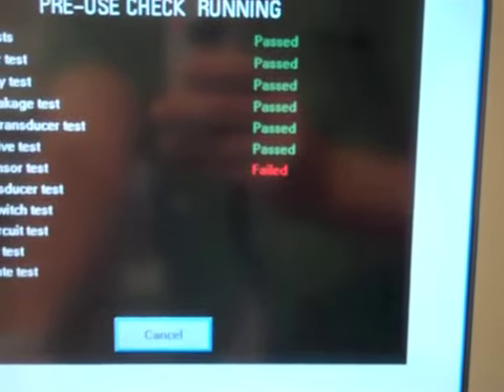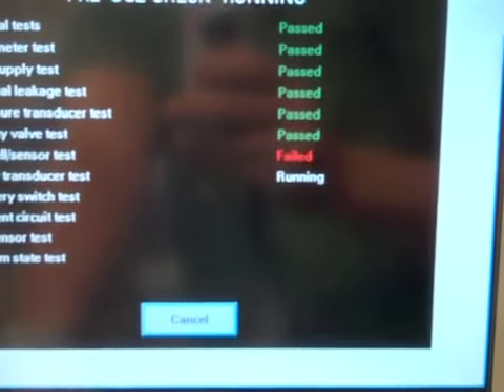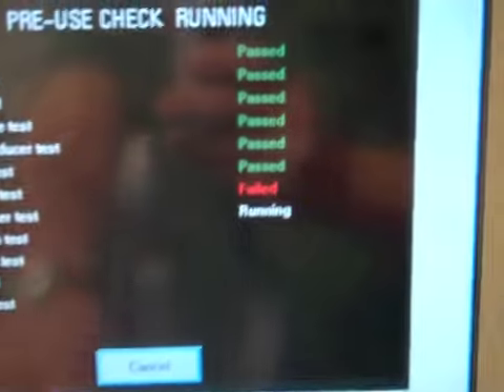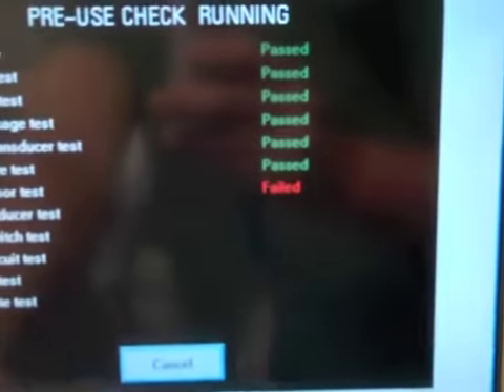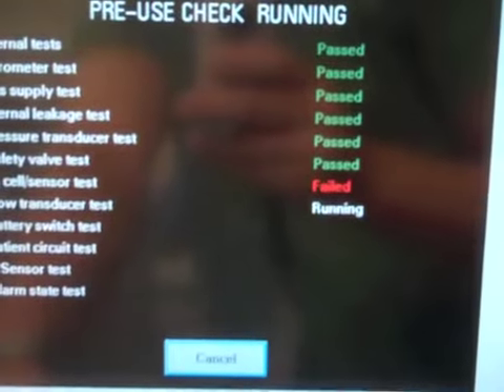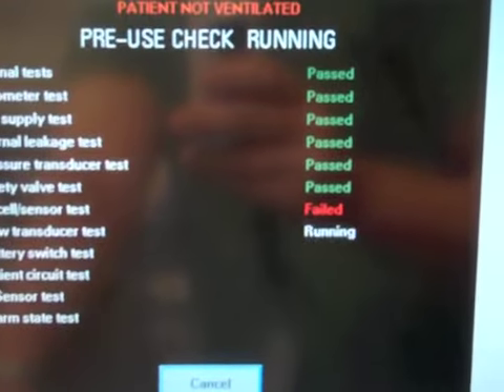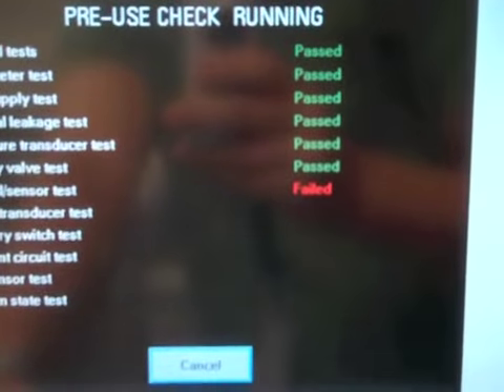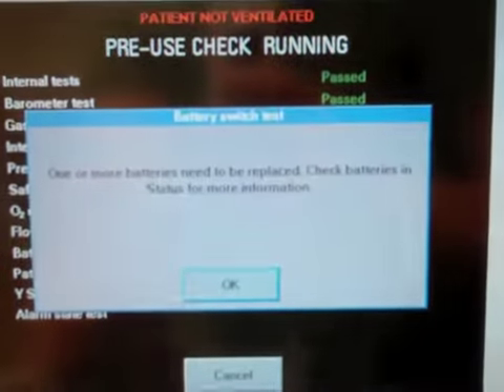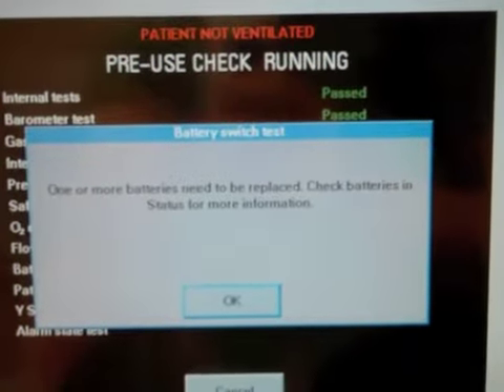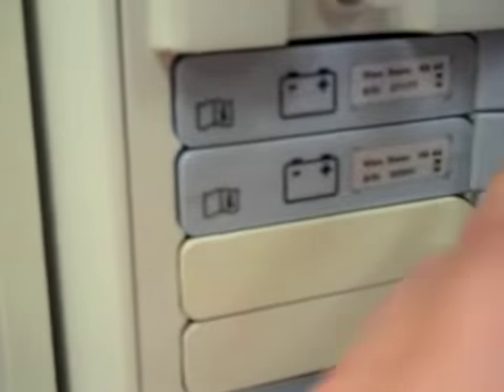I'm going to check my flow transducer next, the battery switch, patient circuit, and the Y sensor and alarm test. So you can see what a failure looks like. It comes up in red. For our purposes, again, in clinic, I would never accept this, but here in the lab, we're going to go with that so we can override this. It says to me, one or more batteries need to be replaced, so check the batteries and the status for more information. The batteries themselves are actually located on the side here as well. So these are the batteries, so you can actually just pop them out, get a new battery and charge them up.